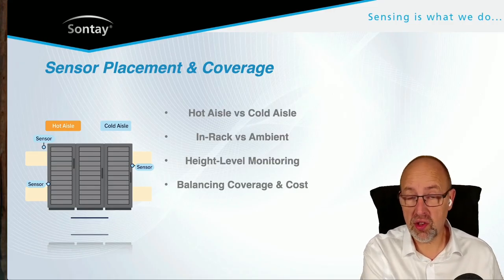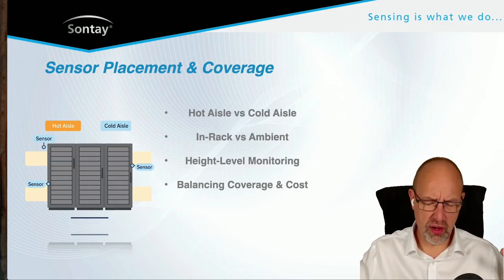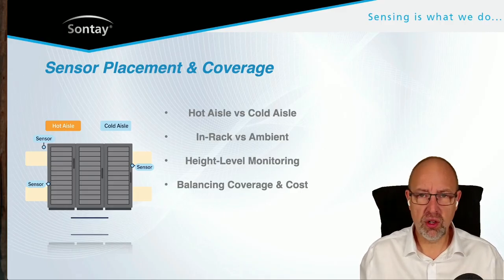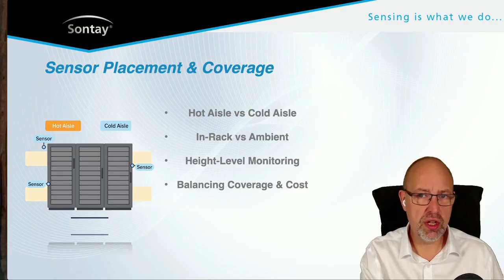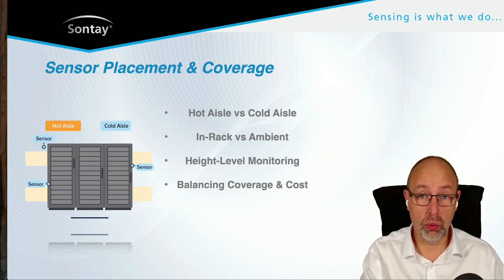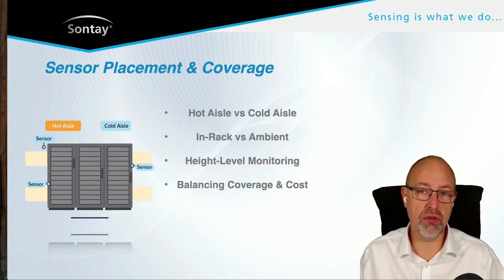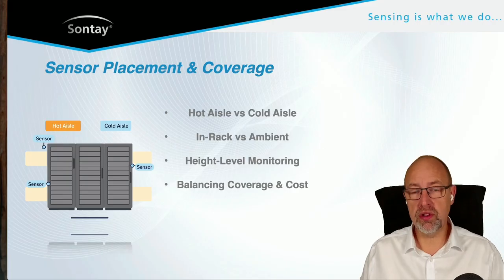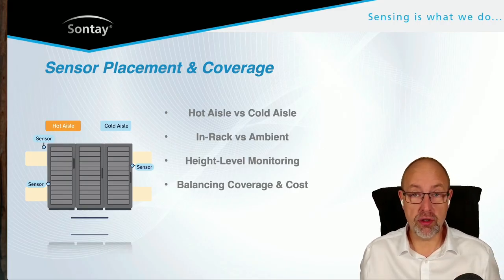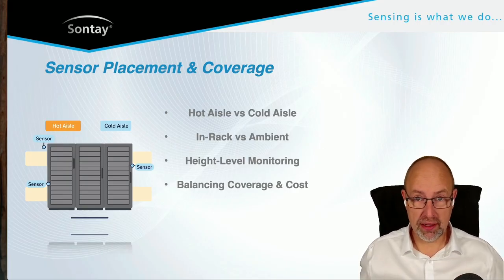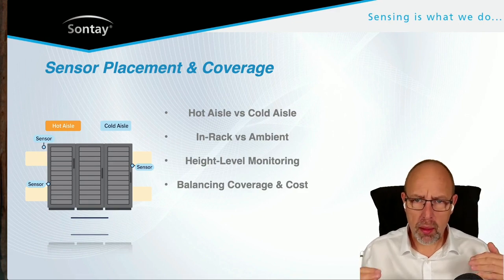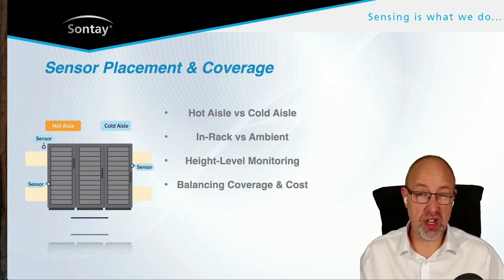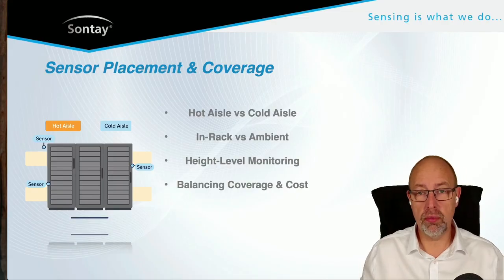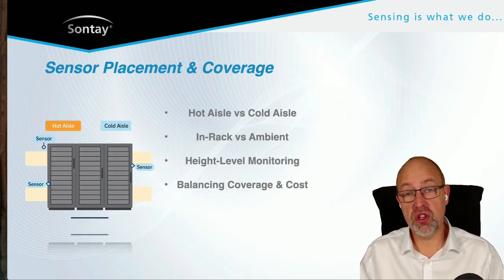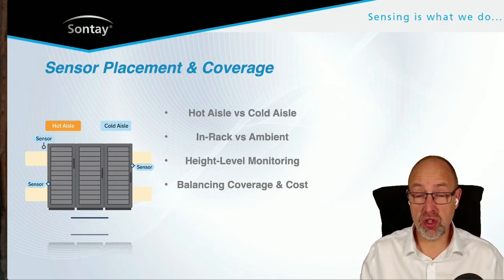Going back to when people used huge Winchester drives, that technology is gone, replaced by modern servers. Those old Winchester drives needed to be kept cool, with the room at 18 degrees C. You wouldn't keep a modern data center at 18 degrees C as standard across the data hall. Modern servers run at higher temperatures, so as equipment is replaced, its operational and environmental parameters change with it.